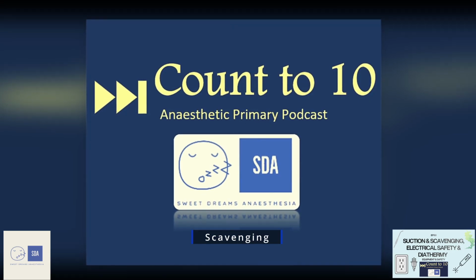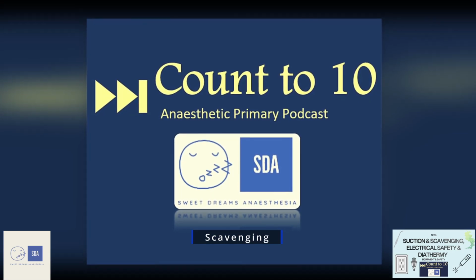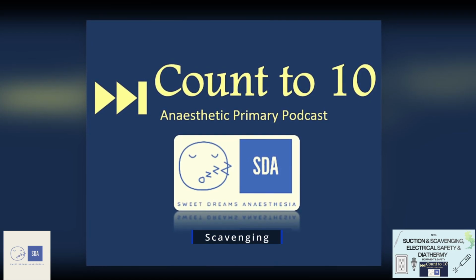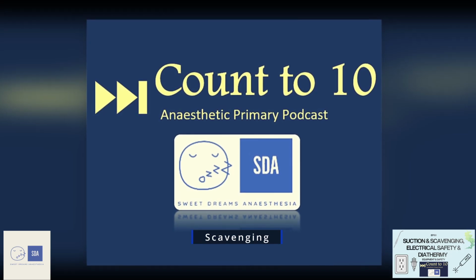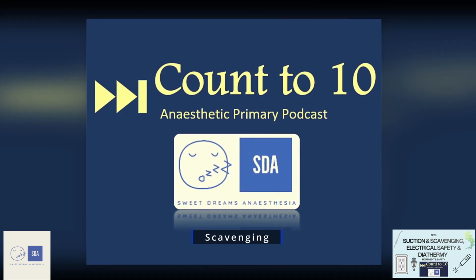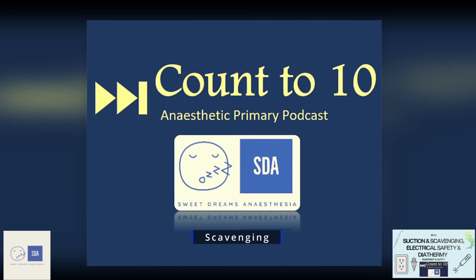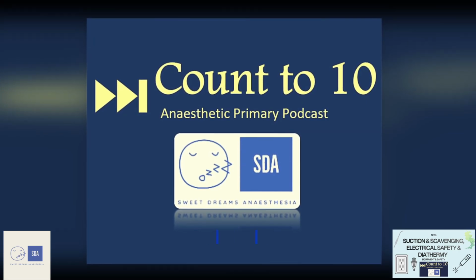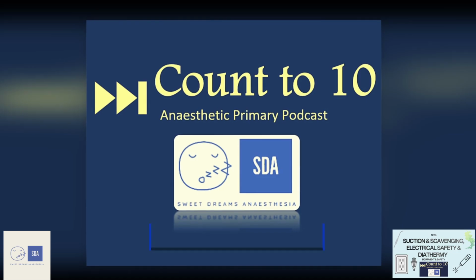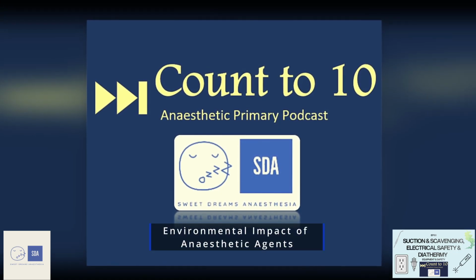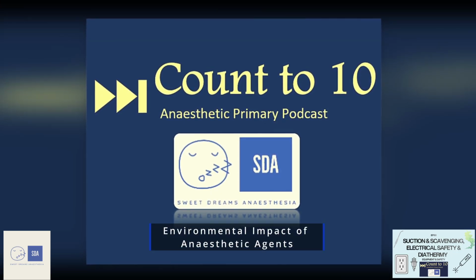Then you have the last component of scavenging, which is the disposal tubing. This is the conduit which moves that waste anesthetic gas to the external environment, typically located at the top of your hospital, releasing that gas into the external environment. And that's a nice segue to look at the second part of this learning objective, which is the hazards of anaesthetic gas pollution.